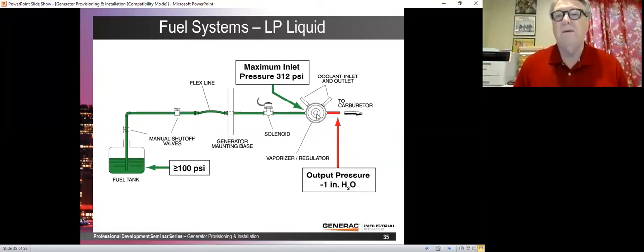And then you can vaporize, and that way you can use very small tanks and still run fine because the vaporization occurs within the generator. And this vaporizer, typically with codes, needs to be mounted outside. So the best thing to do is just mount the generator outside. But if you want an indoor generator and you want a vaporization, then it's a little more complicated. The vaporization has to be mounted outside before it goes into the building.